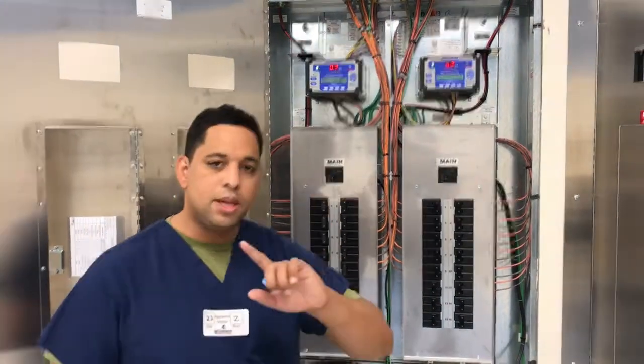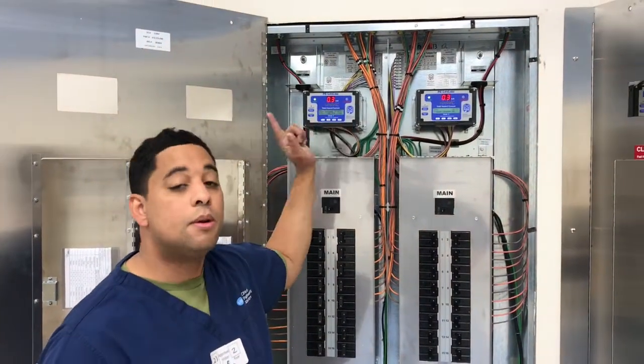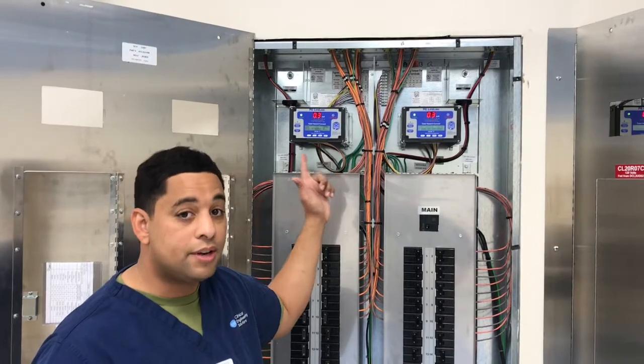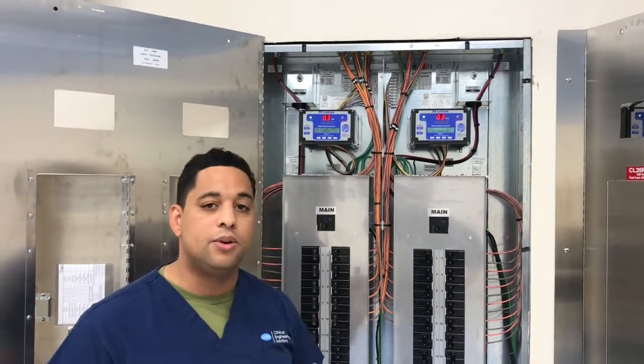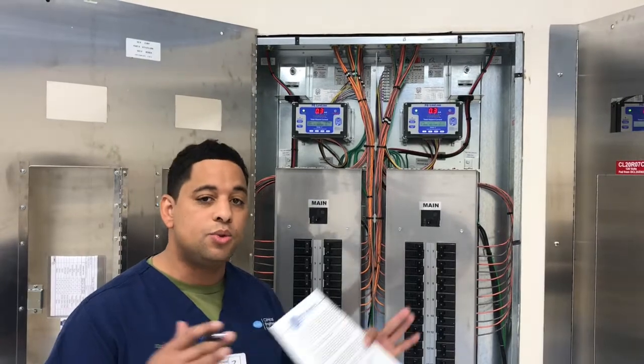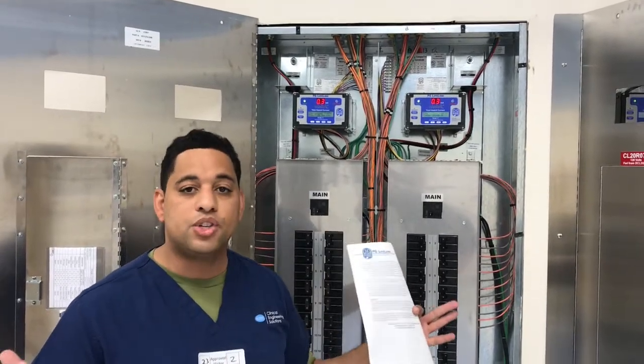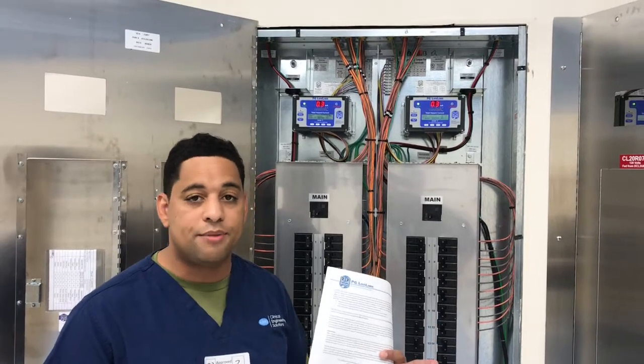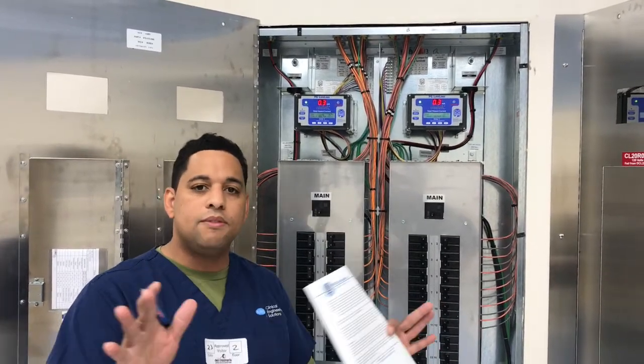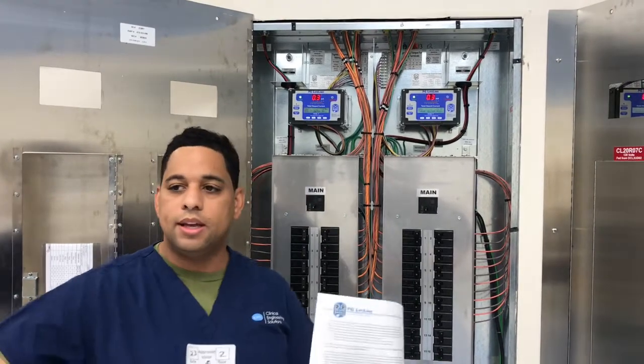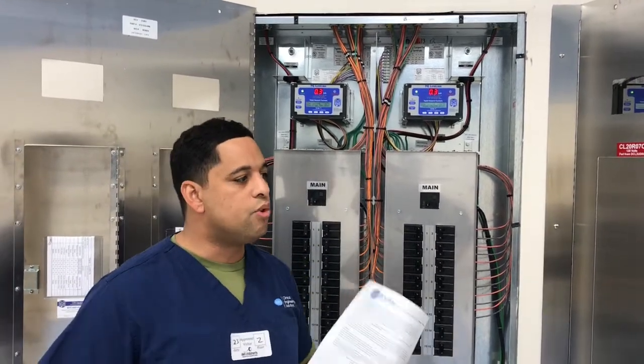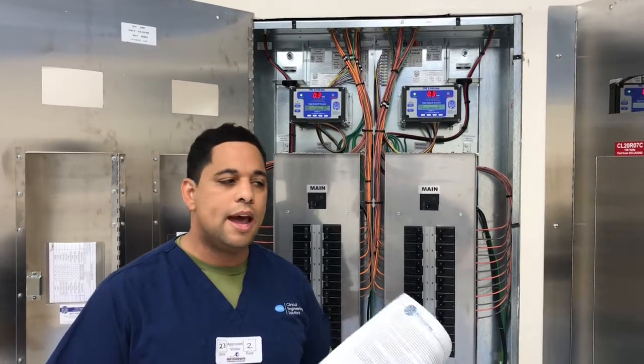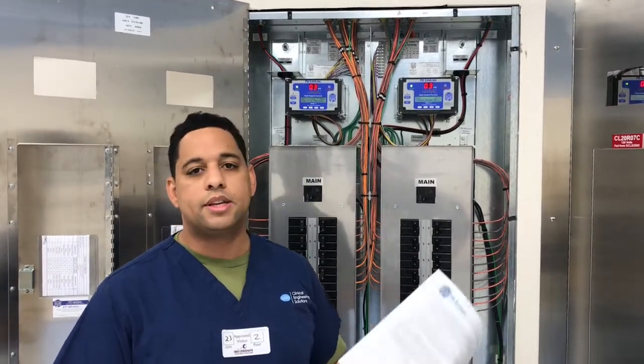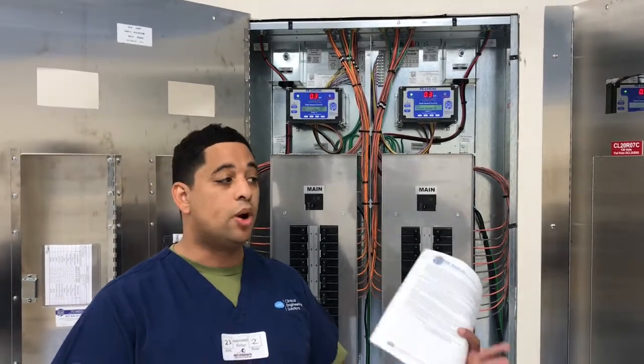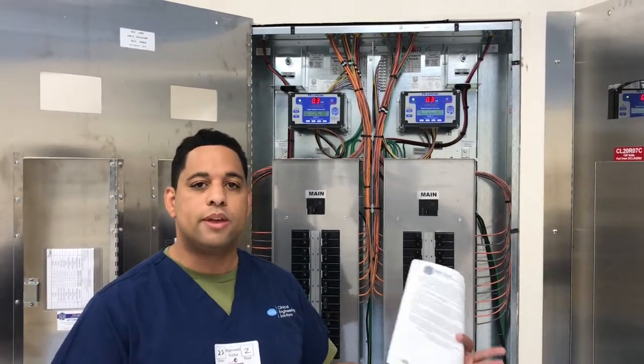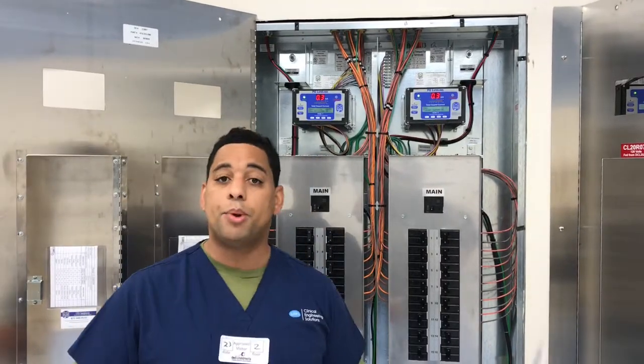So again, key points. You don't need to panic if it alarms, but do call someone if it does alarm, because it is telling you that a device connected to this panel has a malfunction or a circuit malfunction or shorting or whatever. And I'll give you a few examples. You wheel in a stretcher and you run over the power cord with the stretcher. Now you've broken the wire and the wire is exposed. It's going to look like a short and it's going to have more leakage than normal. It's going to alarm.